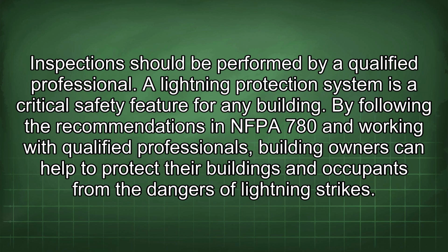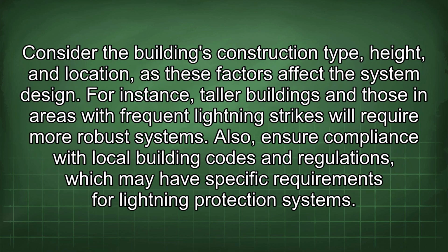A lightning protection system is a critical safety feature for any building. By following the recommendations in NFPA 780 and working with qualified professionals, building owners can help to protect their buildings and occupants from the dangers of lightning strikes. Consider the building's construction type, height, and location, as these factors affect the system design. For instance, taller buildings and those in areas with frequent lightning strikes will require more robust systems. Also, ensure compliance with local building codes and regulations, which may have specific requirements for lightning protection systems.